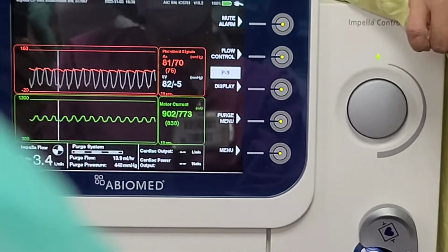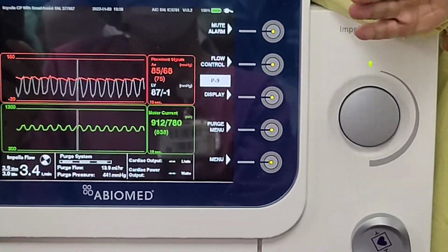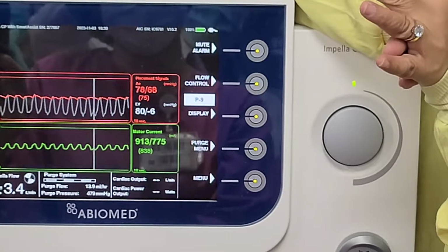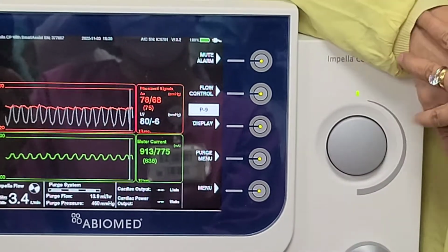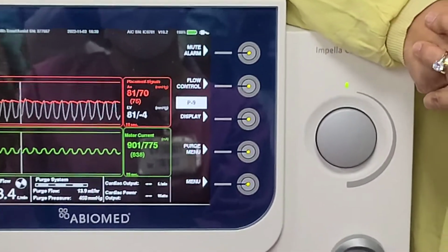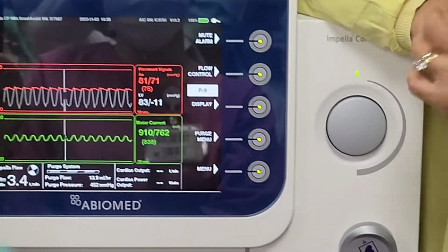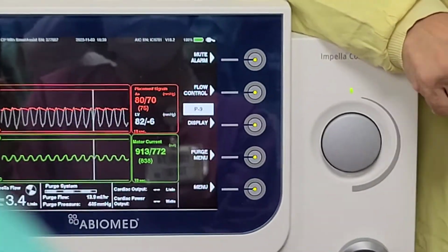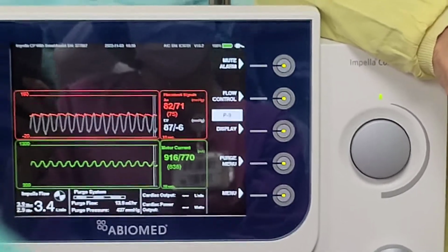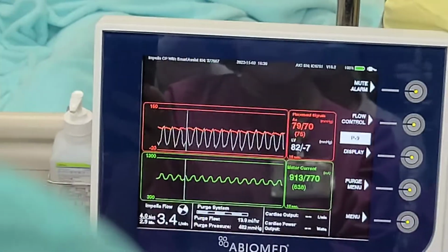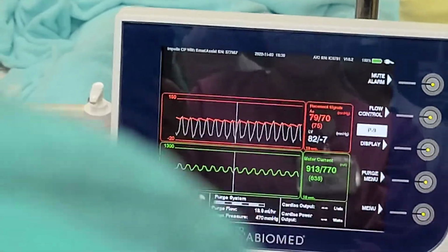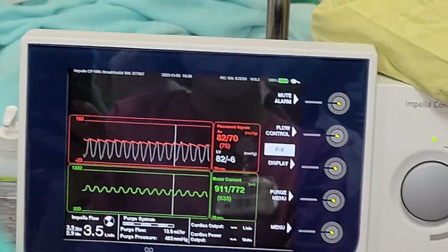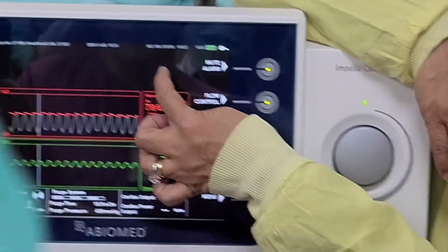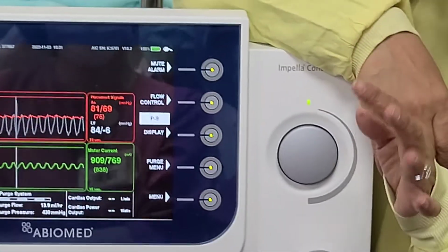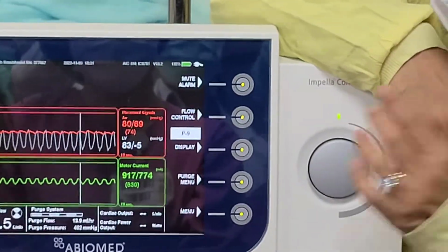The second reason will be position. If your position is against the wall, you will get suction. The third reason, the saddest reason, is right heart failure. That makes it hardest. So these are always the 3 reasons, and you need to be able to determine which is the cause. When the alarm comes out, the alarm will actually give you instructions on what to do, how to troubleshoot. So don't panic. It's quite good. It will give you step by step.